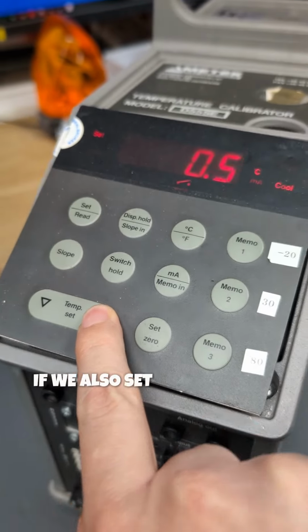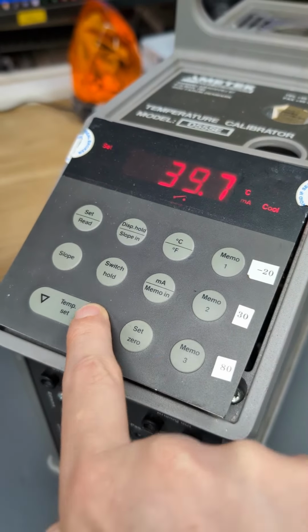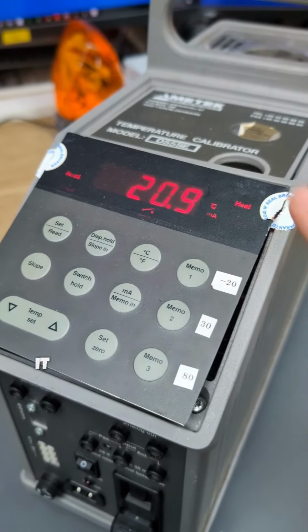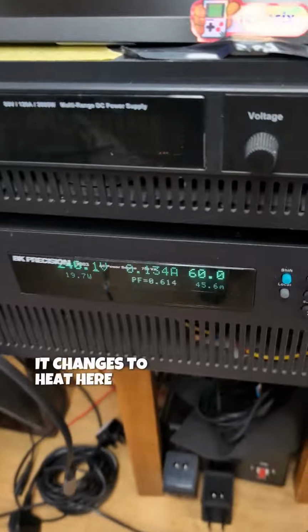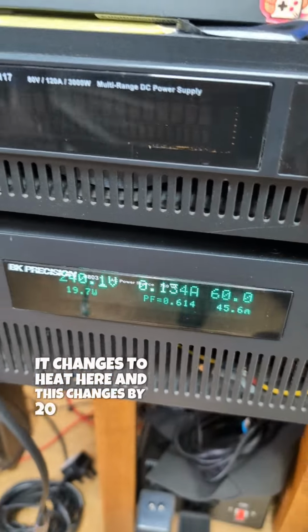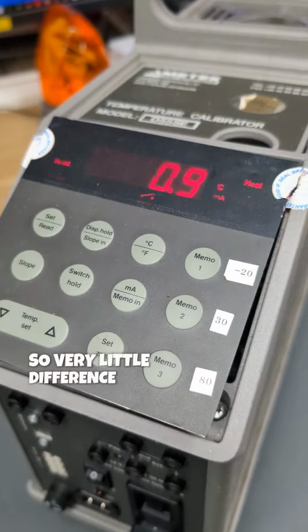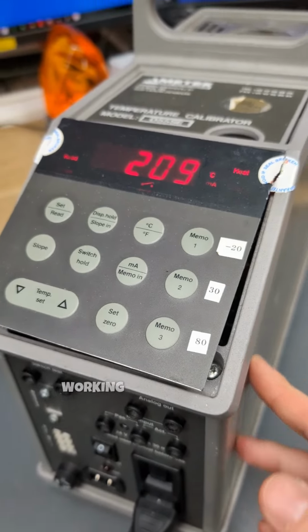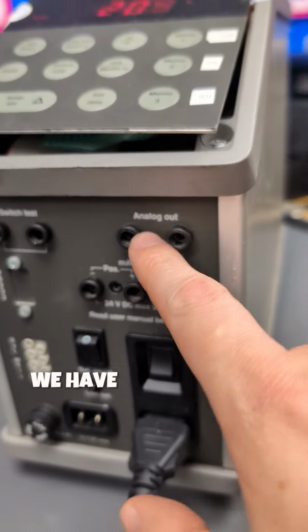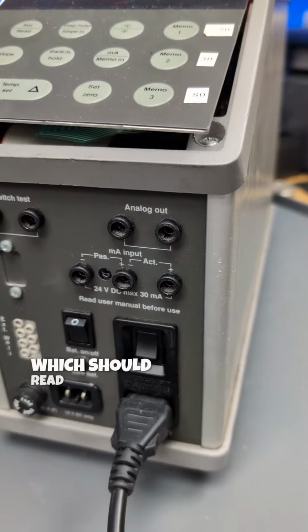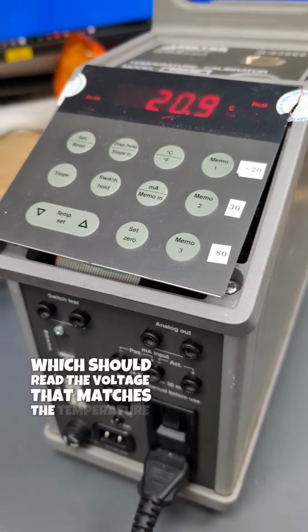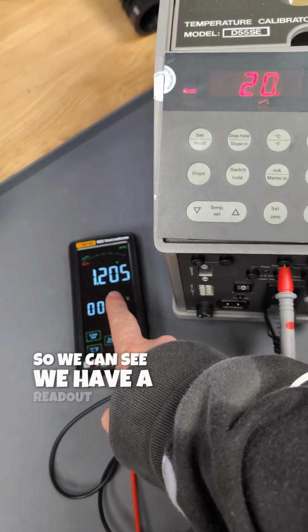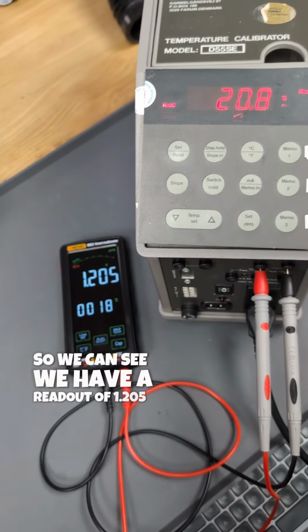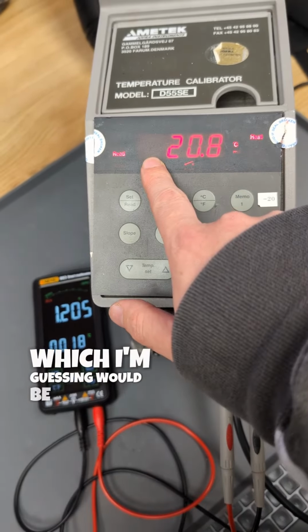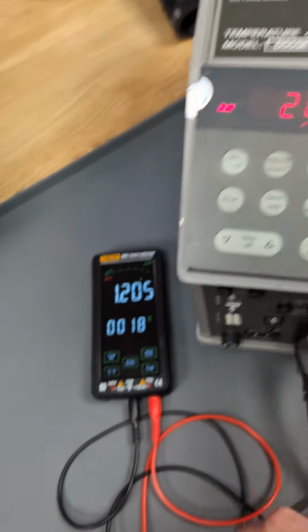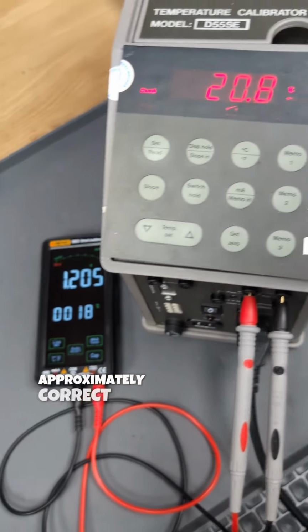If we also set and try the heat, it changes to heat here, and this changes by 20 milliamps, so very little difference, but either way something's not working. We have an analog out here which should read the voltage that matches the temperature, so we can see we have a readout of 1.205 volts, which I'm guessing would be 1 is the offset, 208 is approximately correct.